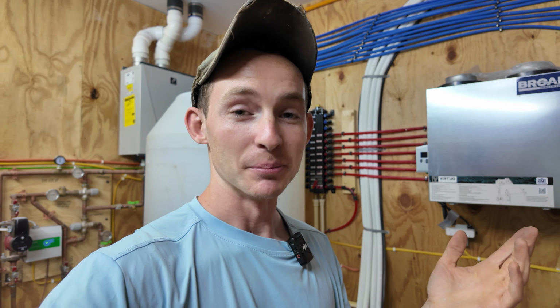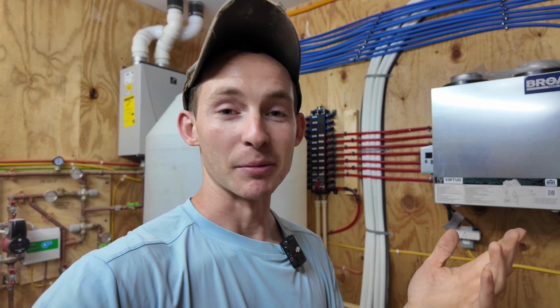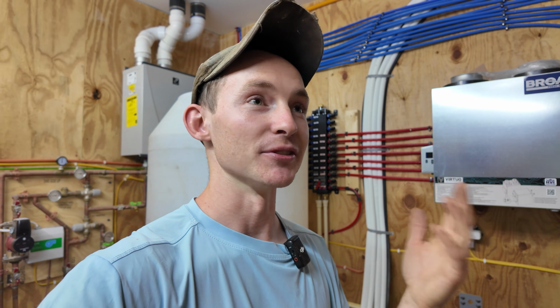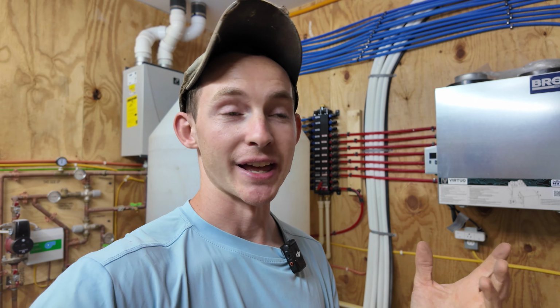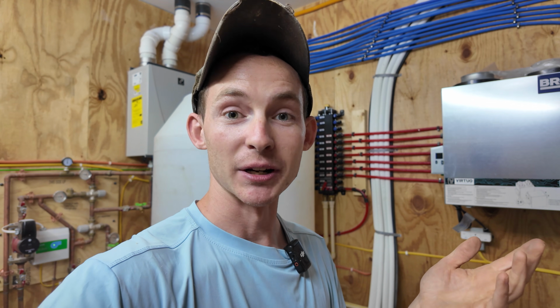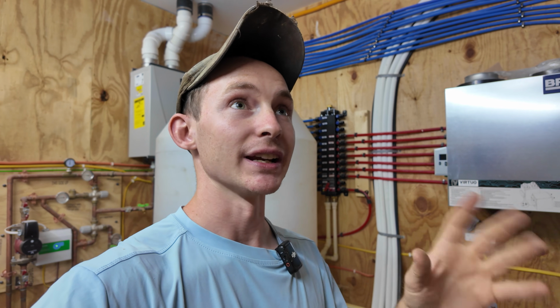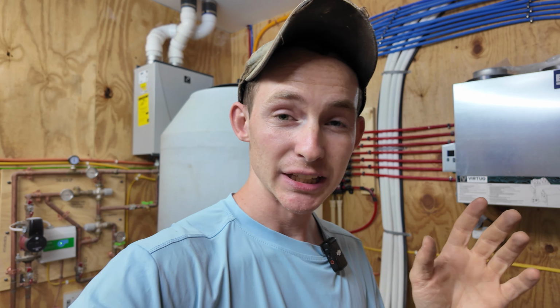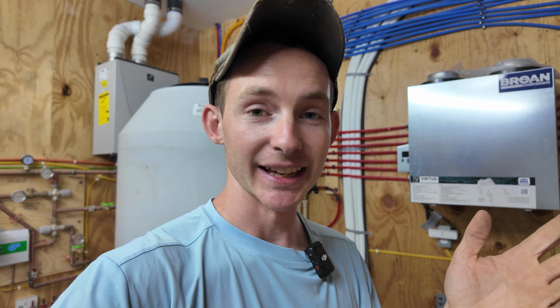It's apparently the biggest complaint about them, and I'm not surprised. It's got a compressor in it just like a refrigerator does, so it's always going to have some amount of vibration when that compressor is running, and this has got a pretty big fan as well. So we're going to see how bad the vibration is from these rigid 2x4 mounts I've made, and they have hanging kits if we need to suspend this from the ceiling. There are I-joists right above it, and we'll hang it from chains. It should be pretty easy to hang it and then remove the supports if we need to.